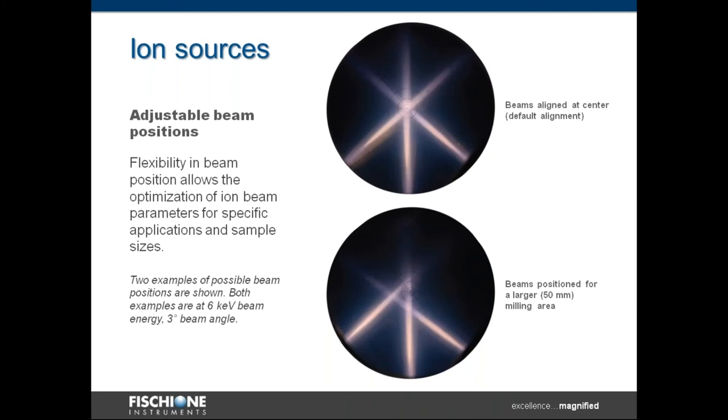This slide shows the relative position of the ion sources and ion beams, and this essentially is the secret sauce of the instrument. If you look at the beams in the upper position, you can see them aligned so that they cross at the center point, which is the axis of rotation. In the lower image, the beams are configured in a birdfoot type of configuration, and that allows the ions to project all the way out to the periphery of the sample. That's what produces the large milling area.